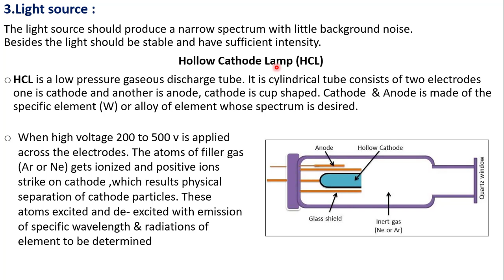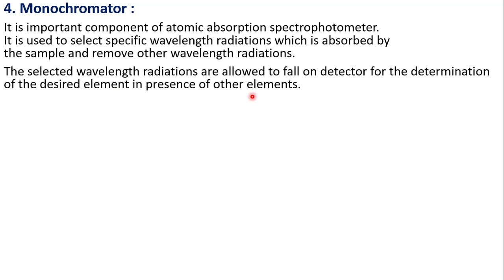Fourth one, monochromator. It is an important component of atomic absorption spectrometer. It is used to select specific wavelength radiations which are absorbed by the sample and remove other wavelength radiations. The selected wavelength radiations are allowed to fall on the detector for determination of the desired element in the presence of other elements. Filter, prism, grating, these are examples of monochromator.